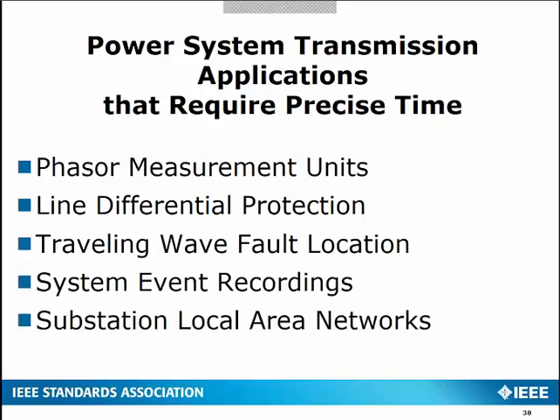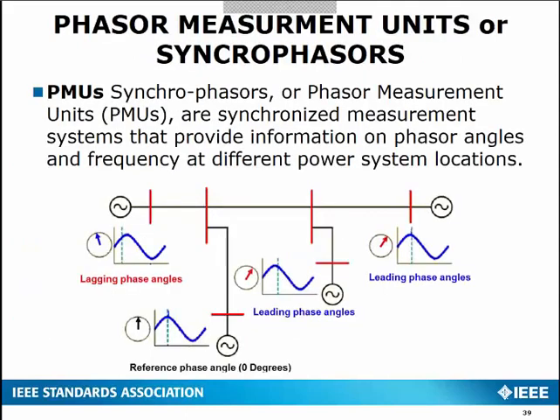The power system transmission applications that we use for precise timing include phasor measurement units, line differential protection, traveling wave fault location, system event recordings, and substation local area networks. Now, first of all, what is a PMU? A PMU is a synchrophasor or phasor measurement unit. It's a synchronized measurement of the system from a wide area that essentially tracks the power flow and the speed of the system, or what we call the frequency of the system.